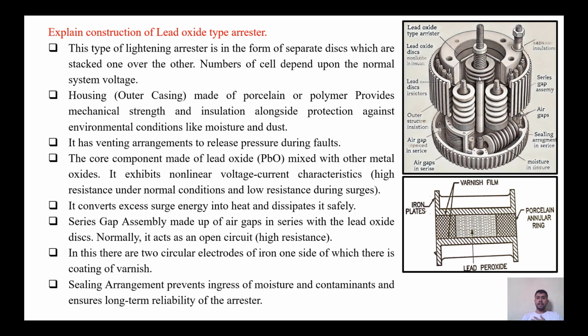Series gap assembly made up of air gaps. So, as you can see here, this series gap assembly made up of air gaps is in series with the lead oxide disc. Normally it acts as an open circuit, meaning offering a high value of resistance in series. In this, there are two circular electrodes of iron, one side of which there is a coating of varnish. Sealing arrangements prevent ingress of moisture and contaminants and ensure long-term reliability of the arrestor.